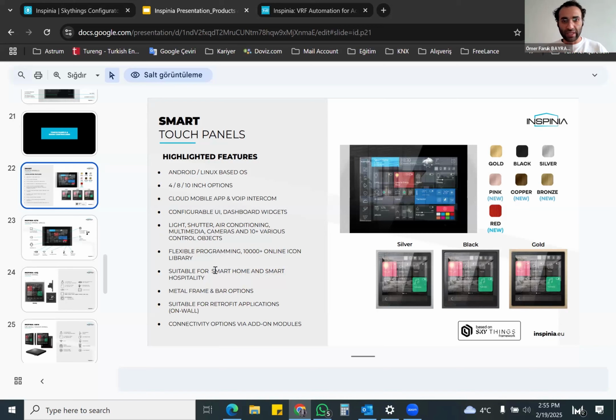After that, you need to understand if you need TCP control or some bus control. If it's bus control, for example, you need to get the Inspinia add-on. After that, you need to know what will be your system's capacity as BMS. If the capacity is not sufficient for your system, you need to increase your BMS license limit. If there is an HVAC solution, you need to know which brand and model, and check compatibility with the checker tool. After that, you will need to obtain an HVAC license, unit or channel. Yes, these are fundamentals of the Inspinia system.